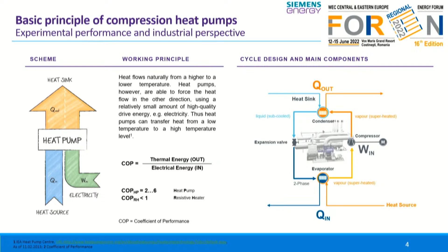You can see here on the right side the main components, how that really works. We have the heat source, on the low temperature level. This is used in the so-called evaporator to evaporate the fluid of the heat pump, normally refrigerants. Then it goes into the compressor to a higher pressure, also increasing the temperature level of the fluid, which can then be used in the condenser to heat up the second cycle of the heat pump. Then it goes back via the expansion valve to the evaporator, and the cycle is closed.